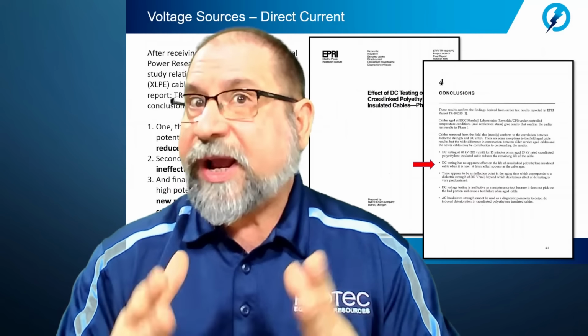Now, the third part of the findings, though, very, very interesting. And again, if you go back to that diagnostic testing of cables part 1, you'll understand more the third bullet point in the EPRI report. Testing a new cable before it has been energized with DC high potential does not cause any reduction to that cable's life. Okay, so again, there are mechanisms that are part of aging that we see in service-aged extruded dielectrics that the DC will actually help to grow and will trigger latent damage into the cable. So, again, for more on the DC testing and the EPRI report, YouTube channel, Protec Equipment, Diagnostic Testing of Cable, Part 1. All right, let's move on a little bit more, though, in this EPRI report.